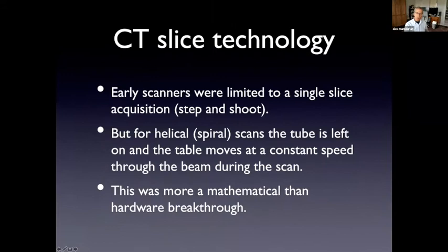And so these early CT scanners were limited to a single slice. Now we use what's called helical or spiral scanning. The way this is done is rather than do a so-called step-and-shoot where we turn the device on, we scan one slice, move on, now this tube is just left on, and the table is moved through the scanner at a constant speed. But this was not really a hardware breakthrough. This was a mathematical breakthrough.